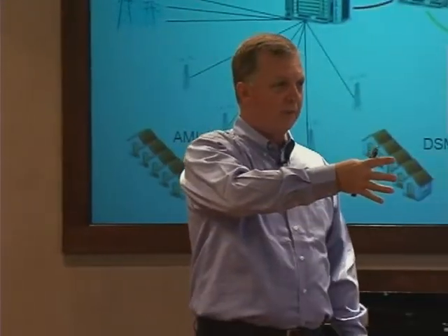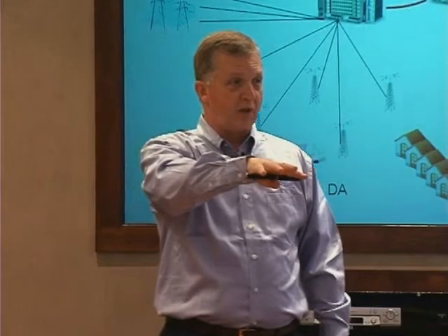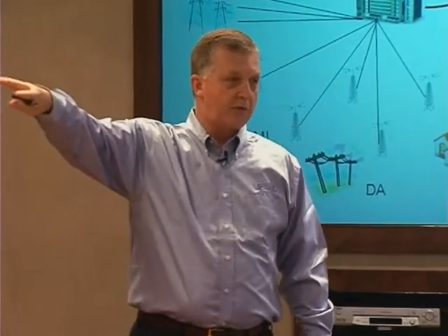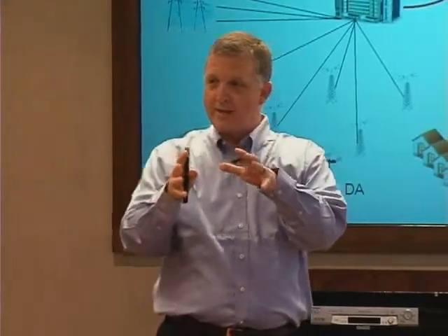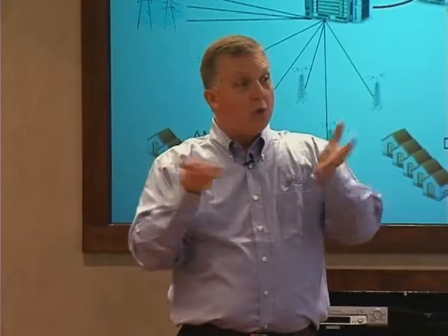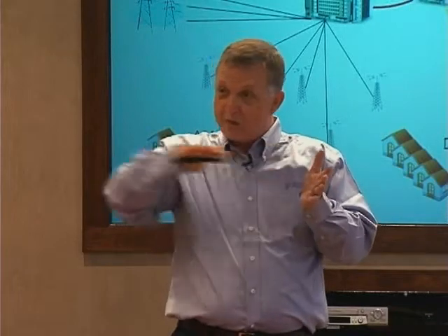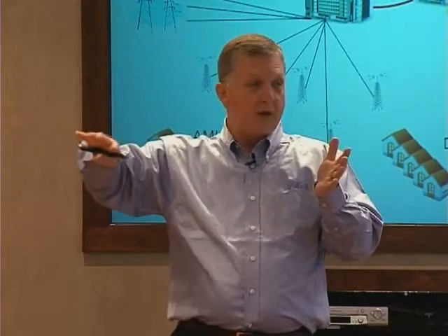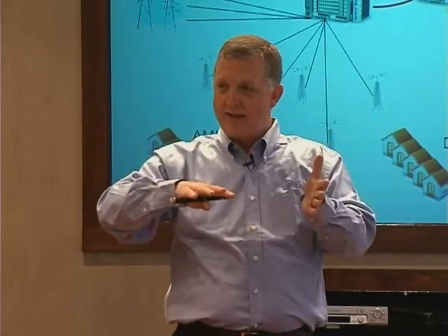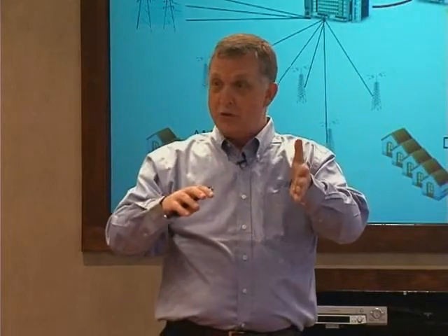Back to the discussion about Mississippi Power earlier, what we had is one of these high-speed backbone routes that went through the coast of Mississippi. It's AFL's optical cable coming from the north, toward Hattiesburg, Mississippi, straight down to the coast, hit our hub point, which was about 5 miles off the coast, and then turned and went to the east toward Mobile. That's that high-speed optical. That's the major tie point into that network. We didn't lose both sides of that ring. We lost one side of it. That side went across through Pascagoula. We did have some structures damaged through there. But because we had that alternate path, we maintained connectivity from the outside world into the coast of Mississippi because of that backbone.